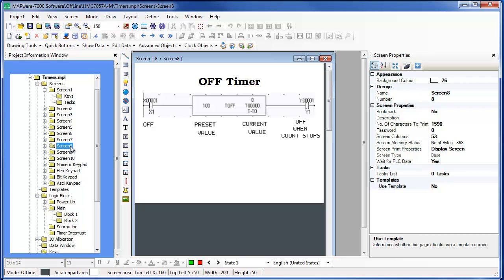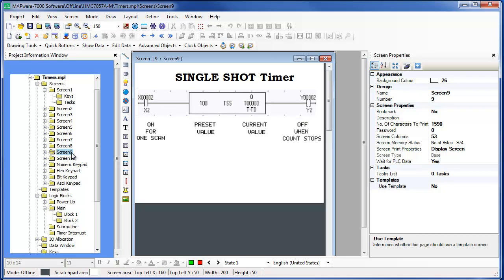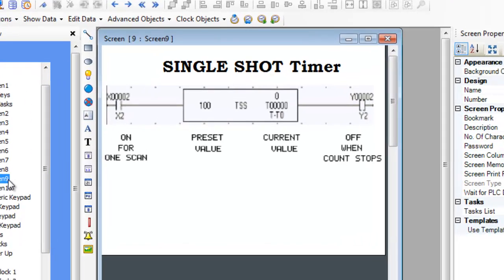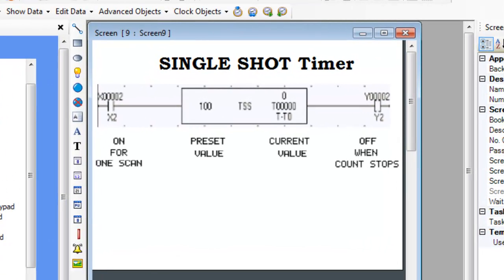A single shot timer counts while the input is on. Unlike the on timer, this timer continues to count even if the input is reset to off — hence the name single shot. Therefore, this timer can be used with a momentary input contact. When the preset time value is reached, the timer stops counting and the output turns off. While the timer is counting, the output is set on.